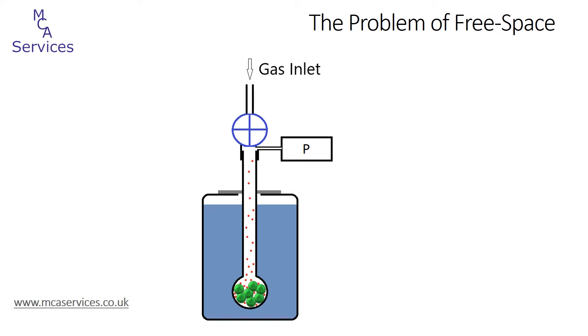Free space at the analysis temperature is not the same as the empty tube volume at room temperature, because there's a thermal gradient along the length of the tube. The bottom part is at 77 kelvin whereas the top part is closer to ambient. Thankfully the analysis will include a step for the measurement of free space, usually taken before commencing dosing of the adsorbate, and that takes care of both the room temperature and the 77 kelvin components.